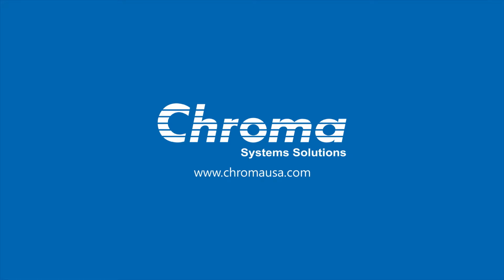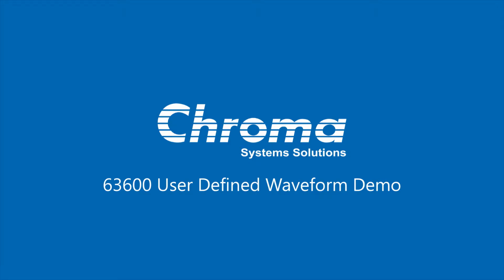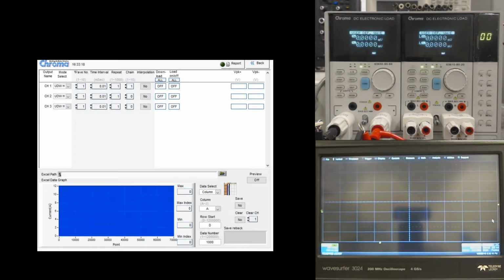Hey everyone, today I'll be showing you one of the most powerful features of the 63600 electronic loads, the User Defined Waveform feature. This feature will allow you to upload an arbitrary loading waveform to the unit using an Excel file. On the left is the soft panel, which is used to control the 63600 loads via USB.